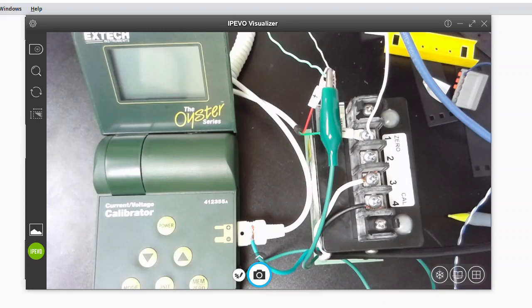In this procedure, we're going to actually be using a 0 to 10 volt signal. We're currently moving away from those, but we still have some older processors and cards, and they're still using 0 to 10 volts, so you will run across that. So we're going to use a single phase voltage transducer from Ohio Semitronics that has a range of 0 to 600 VAC and outputs a 0 to 10 volt VDC signal.